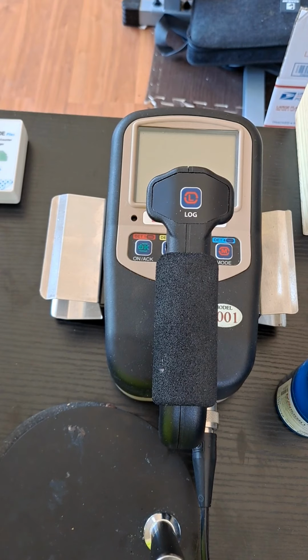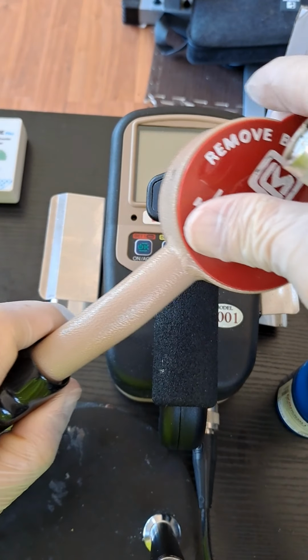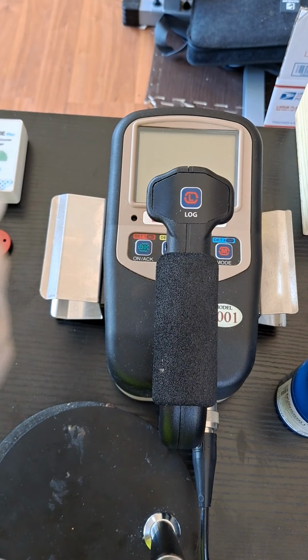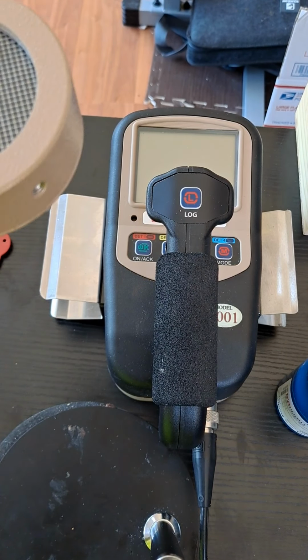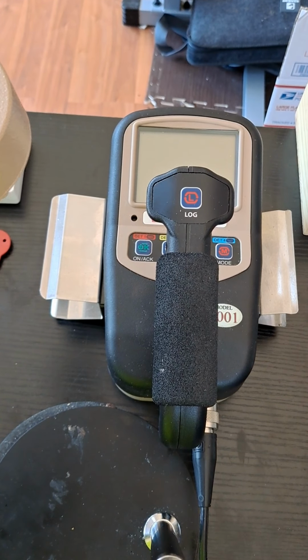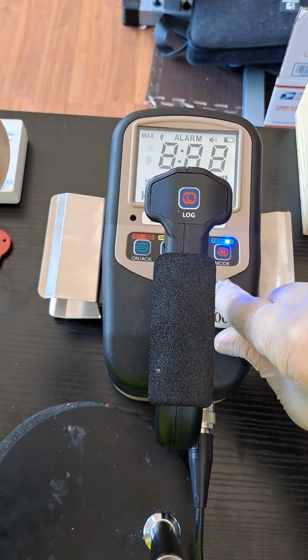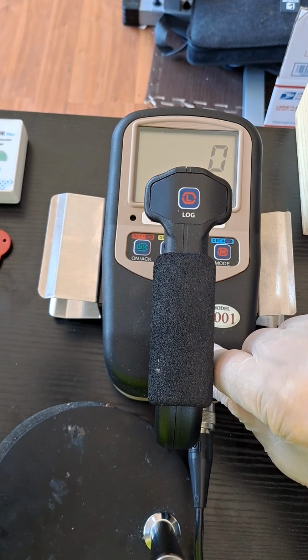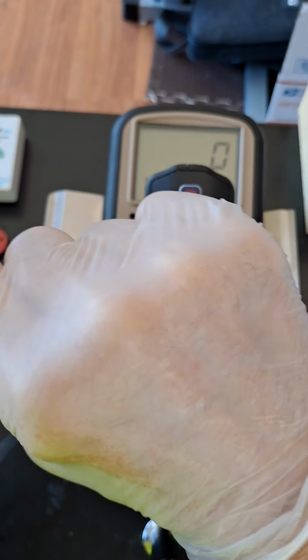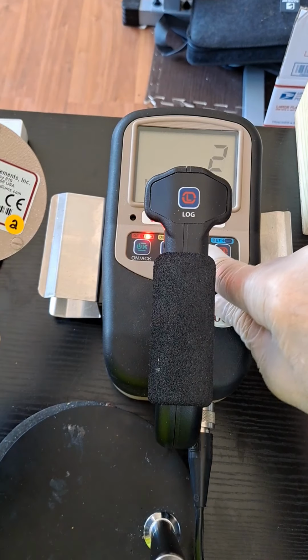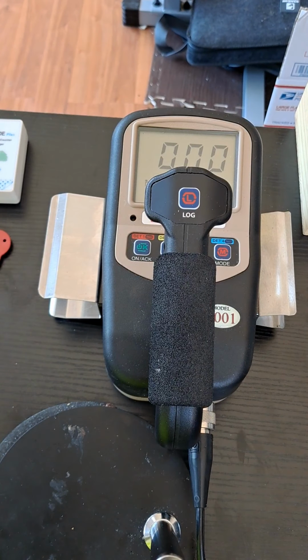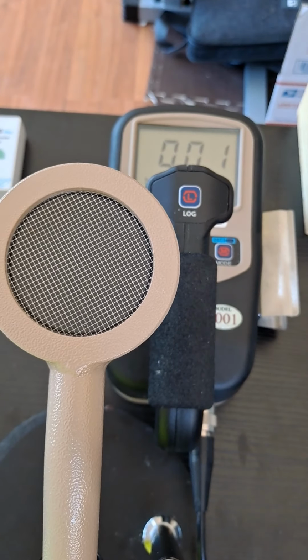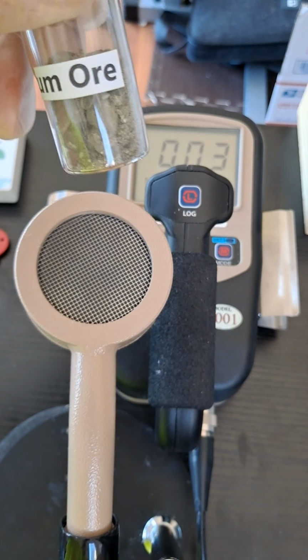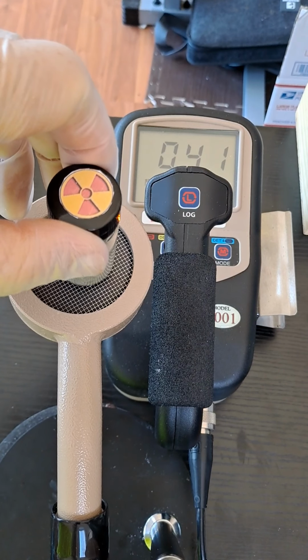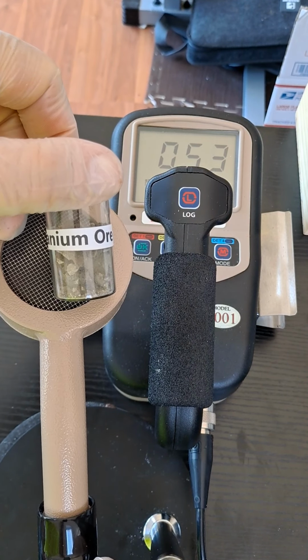The next instrument we use is what's called a frisker. This is how we keep track of alpha, beta, and gamma. I switch the connectors and turn on the instrument, and I then switch. It goes by the color. See the color here? It's yellow. I push the mode for the yellow. Now it's using this instrument. Then this can detect both alpha, beta, gamma. In my uranium ore, which I have right here, I put it on here, and it's detecting. You can tell by the sound.